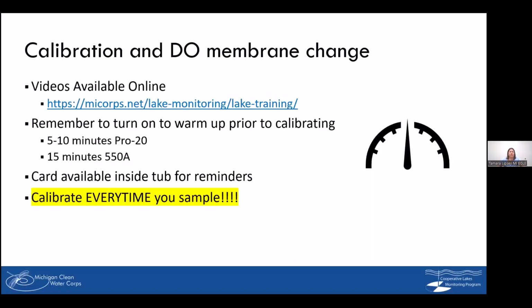So that video is available online. I hope to update the membrane changing one with the Pro 20 as well. Just remember to turn on your meter for 5 to 10 minutes with the Pro 20, more like 15 with the 550A, so that it's warmed up prior to calibrating. There's a card inside the tub for reminders, and you need to calibrate every time you sample. I calibrate every time I sample. It's important to make sure your meter is working correctly so that you have accurate data.